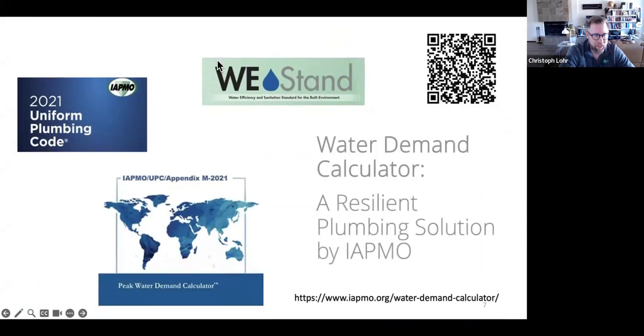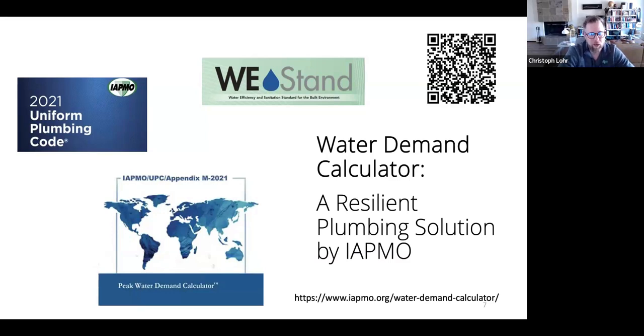So starting in 2017 with the Water Efficiency and Sanitation Standard, and then following suit in the 2018 Uniform Plumbing Code, and since adopted in the 2021 and 2024 Uniform Plumbing Codes, it has been separated into its own standalone document that you can see there, IAPMO UPC Appendix M 2021. The Water Demand Calculator was released, and this was the first time in about 80 years that we have right-sized and really much more accurately estimated the peak flow rate.